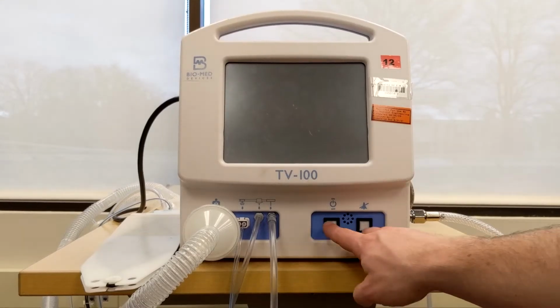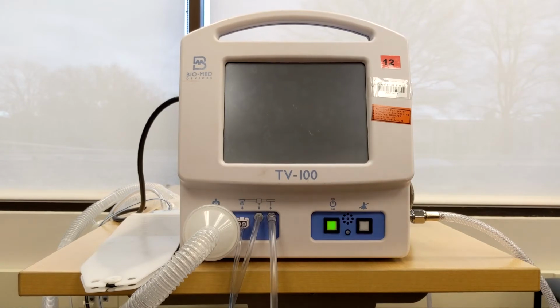Press the power button for a few seconds until the ventilator powers on. At power on, the TV-100 will perform a power on self-test. The power on self-test checks all microprocessors, all pressure and flow sensors, all valves, and memory. If the power on self-test fails, the TV-100 will display a warning pop-up with alarm message.